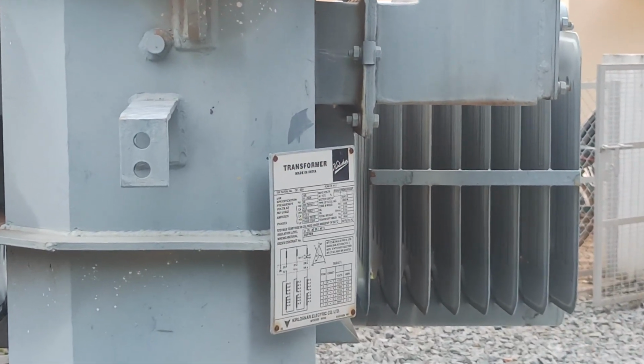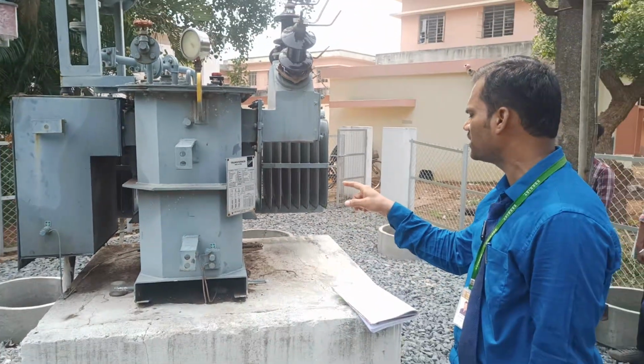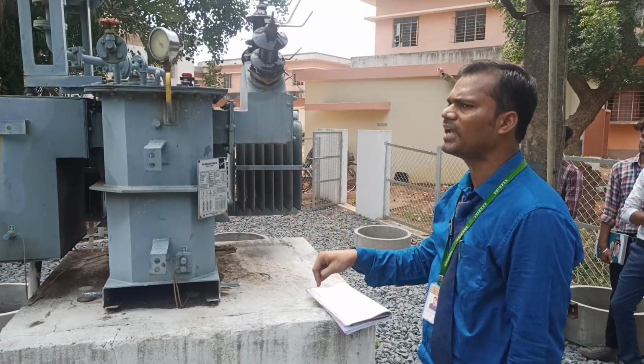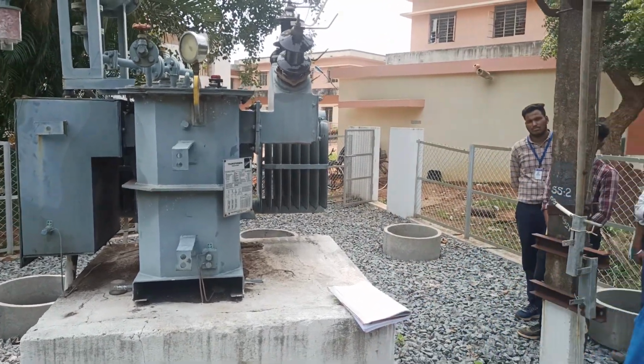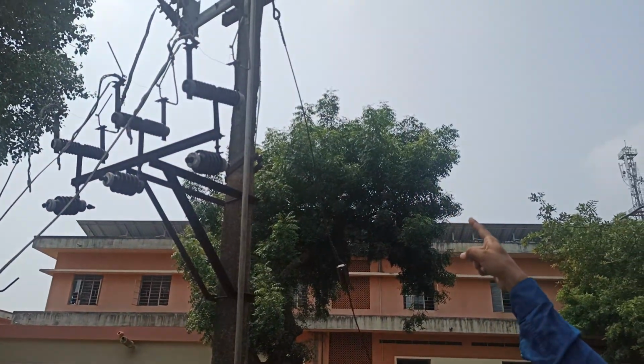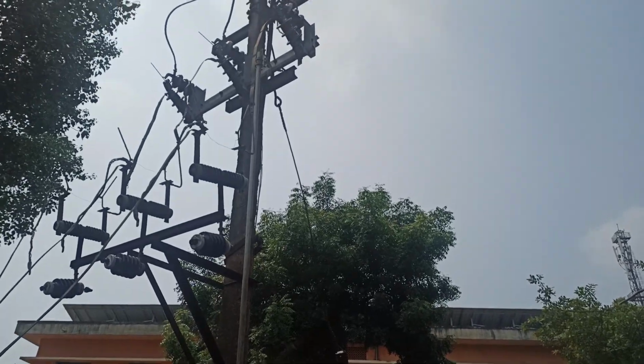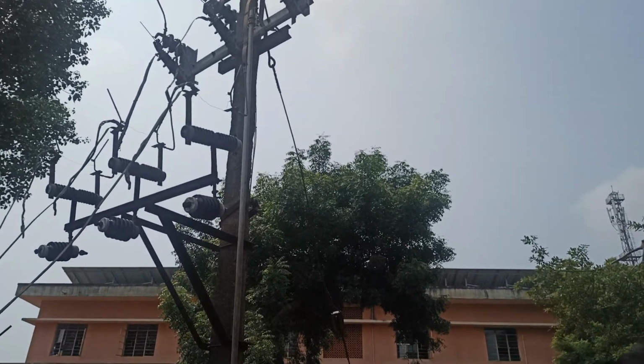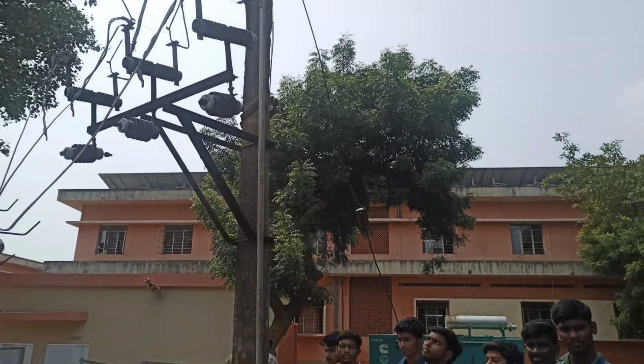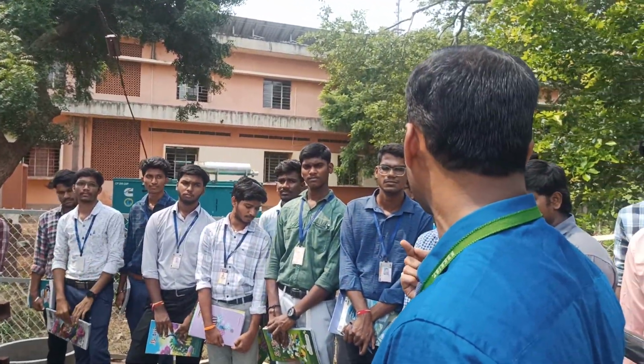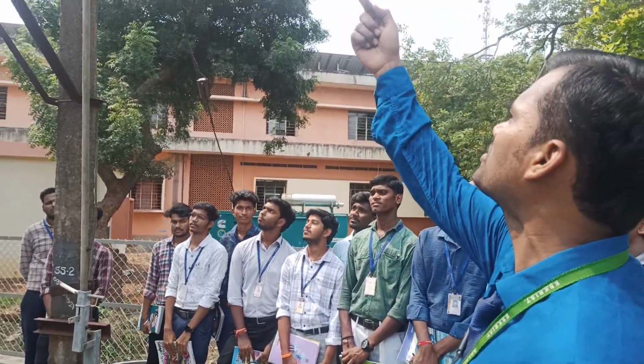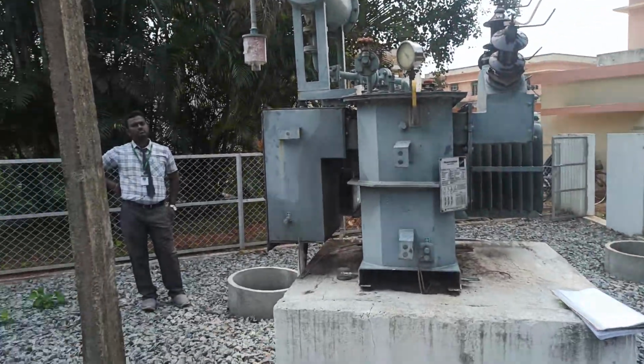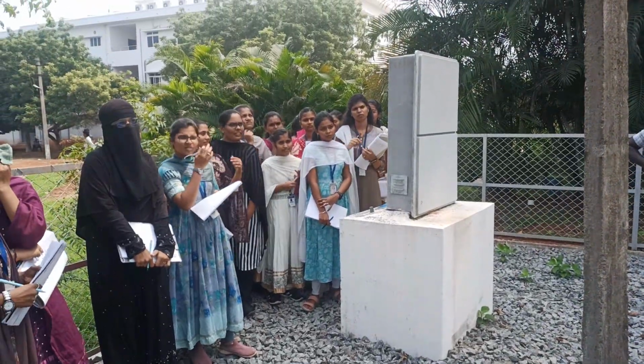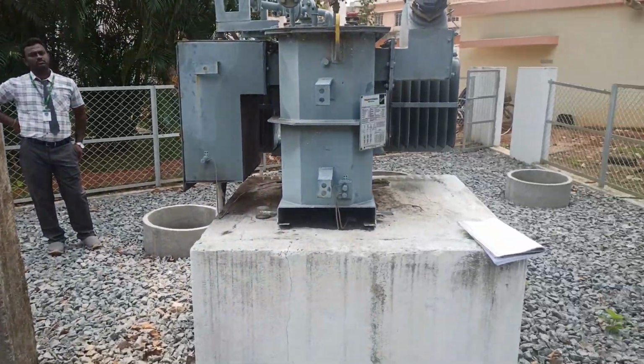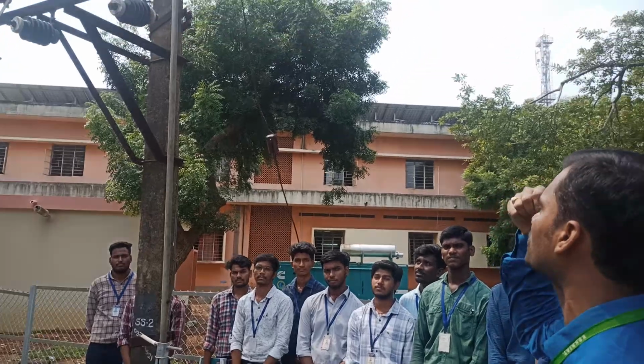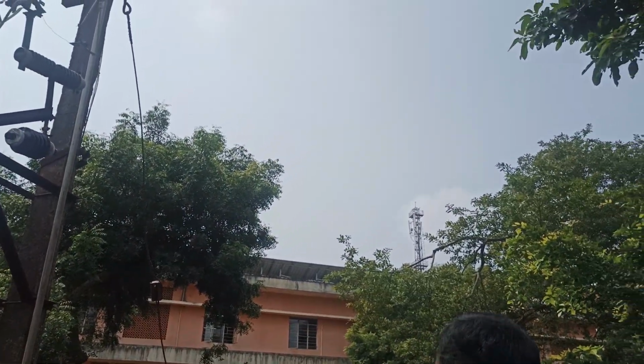Voltage is high, so automatically current will be lower. So input voltage is 11 kV and current is 8 amperes. Since current is 8 amperes, you see the fuses are very thin. Why? Because the maximum withstand capability is 8 into 1.5. 8 into 1.5 means 8 plus 4, it's how much? 12 amperes. Maximum it can withstand a current of 12 amperes. Input voltage is how much? 11 kilovolts, but current is how much? 8 amperes. So on average and at full load also it can take only 12 amperes.